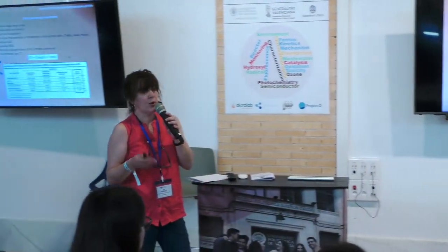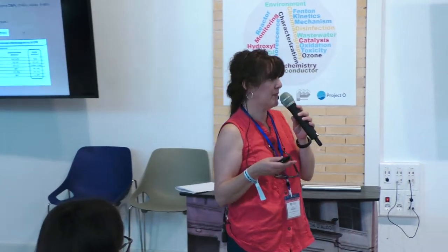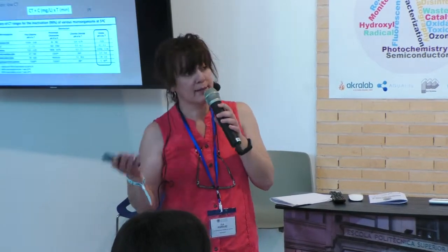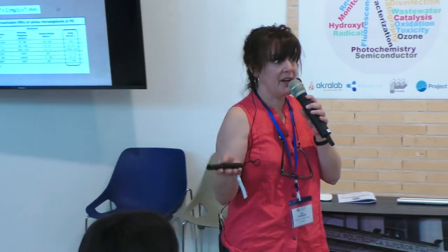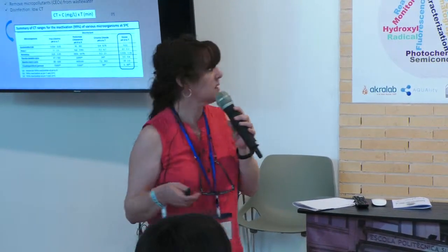What we do is oxidize the compounds responsible for these organoleptic properties, or avoid their formation. To oxidize iron(II) and Mn(II) to insoluble oxides that are later easily removed by flocculation, coagulation and sedimentation. To improve flocculation, allowing lower doses of coagulants.